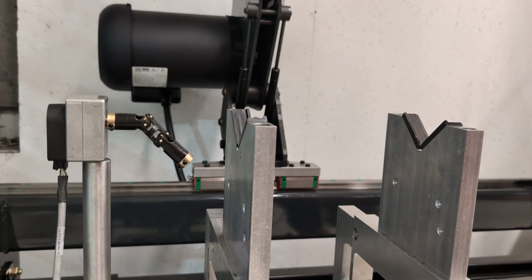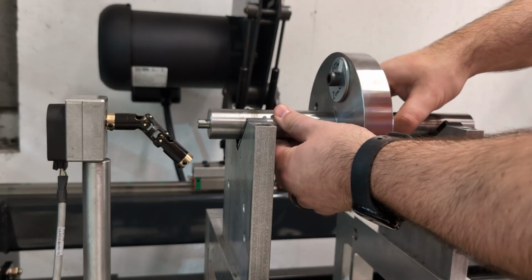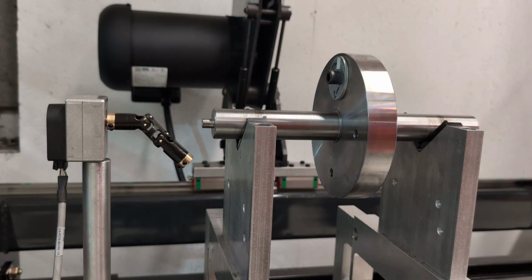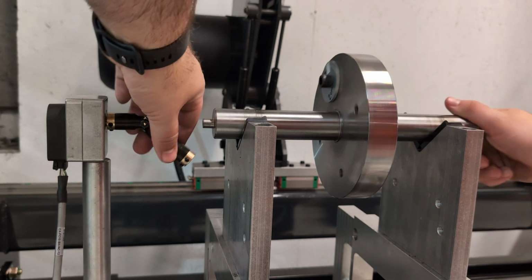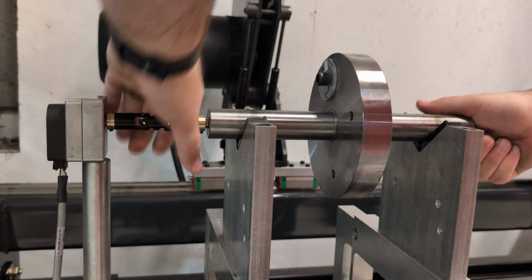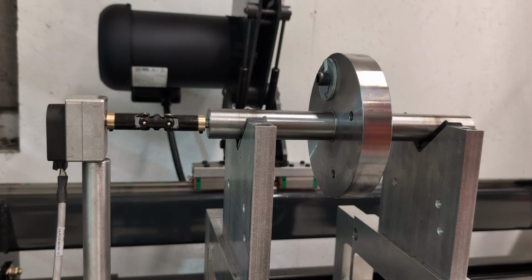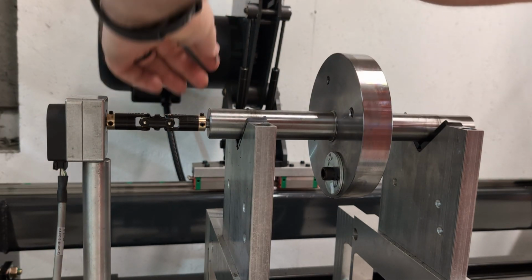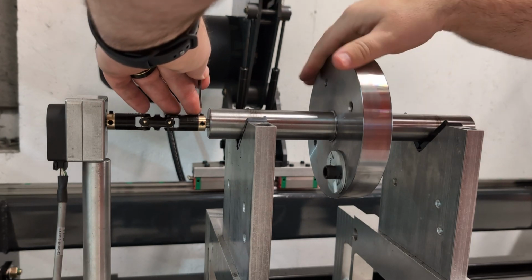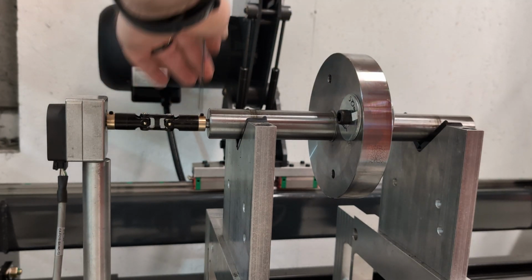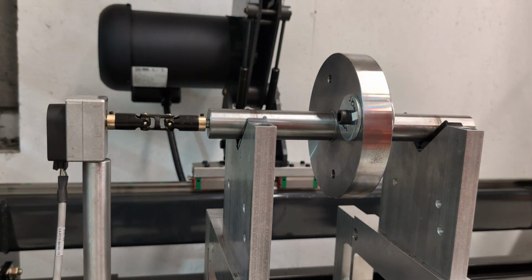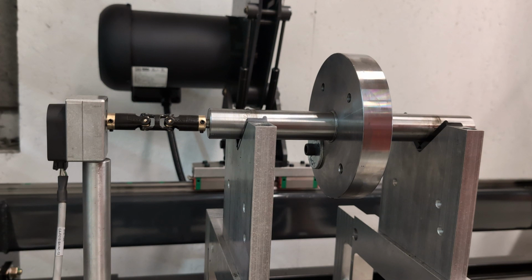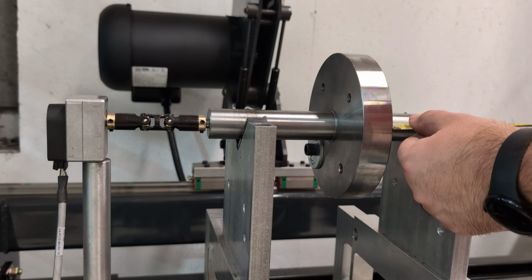Begin by turning on the computer and mounting the calibration arbor on the machine. Attach the encoder directly to the arbor by sliding the U-joint onto the turned-down portion of the arbor. Secure it with the 2 set screws. Make sure that the arbor is centered as closely as possible between the 2 columns. This positioning is crucial for accuracy during calibration.